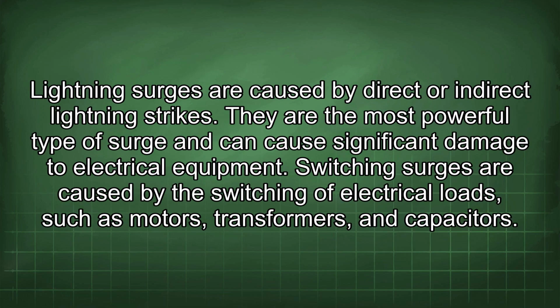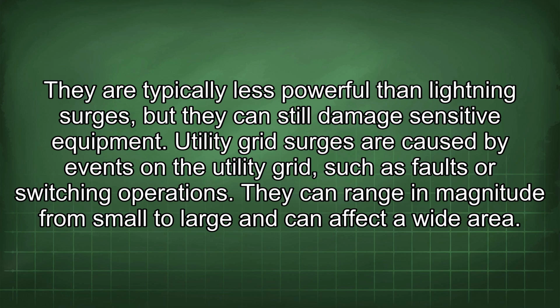Lightning surges are caused by direct or indirect lightning strikes. They are the most powerful type of surge and can cause significant damage to electrical equipment. Switching surges are caused by the switching of electrical loads such as motors, transformers, and capacitors. They are typically less powerful than lightning surges, but they can still damage sensitive equipment. Utility grid surges are caused by events on the utility grid, such as faults or switching operations. They can range in magnitude from small to large and can affect a wide area.